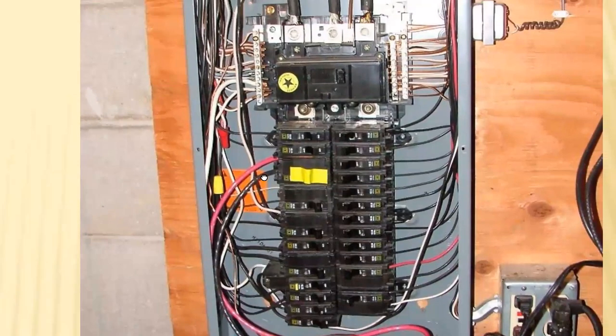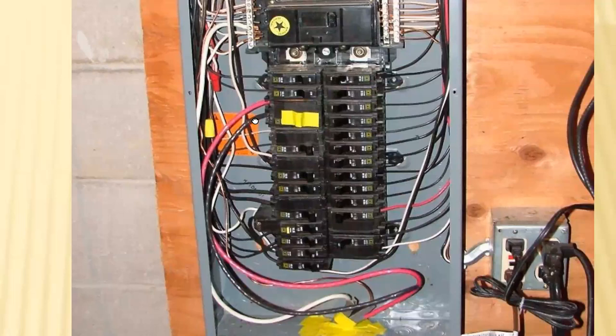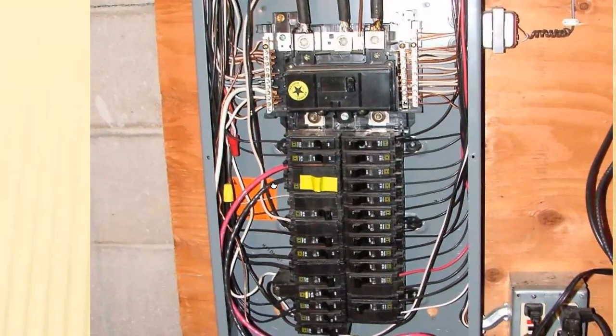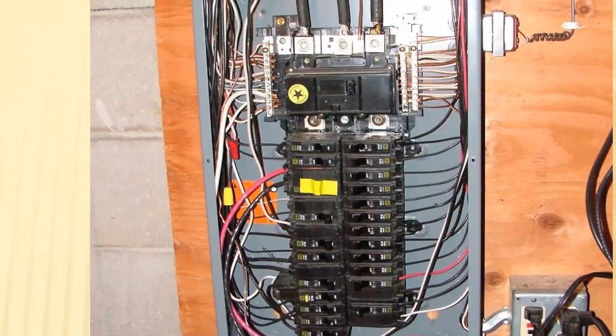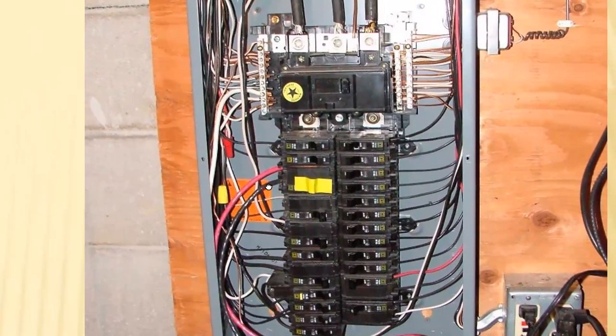Let's say here is the distribution panel. The distribution panel will have a grounding bar where all the grounds will be connected together. In this one here, you can see the grounds and some of the neutrals are connected together. So let's say this bar is connected straight into something that's called a true ground. It could be a plate driven into the ground outside. It could be a spike driven into the ground outside. And there are certain ways that it has to be done. Or it will be something that's labeled as true ground on the construction site in that room.